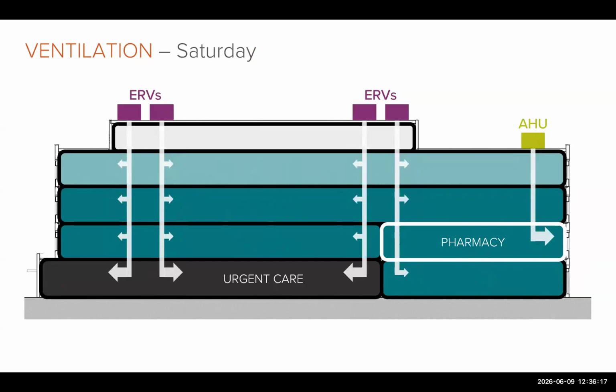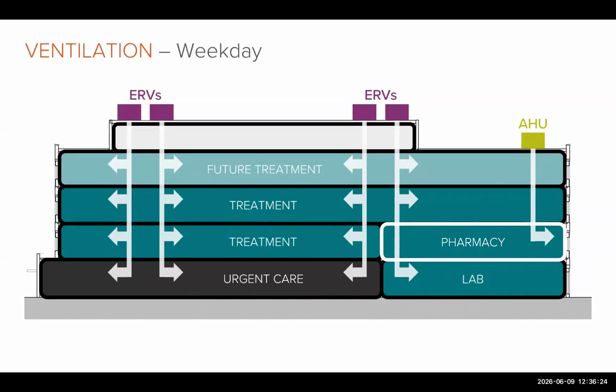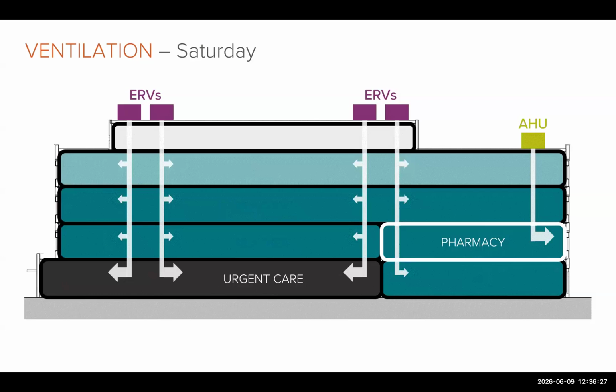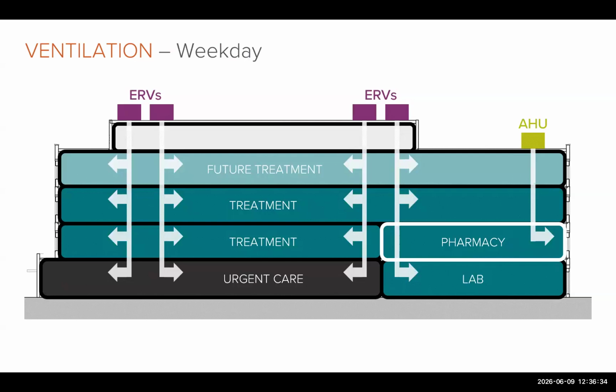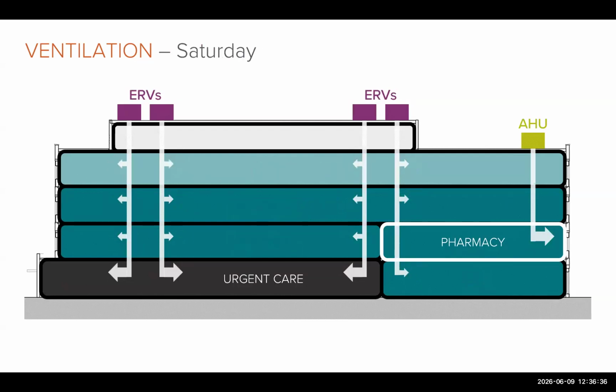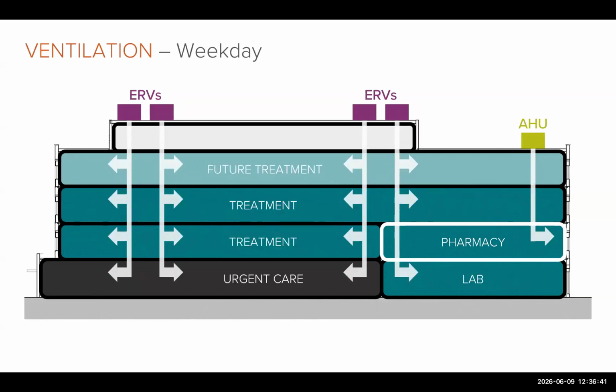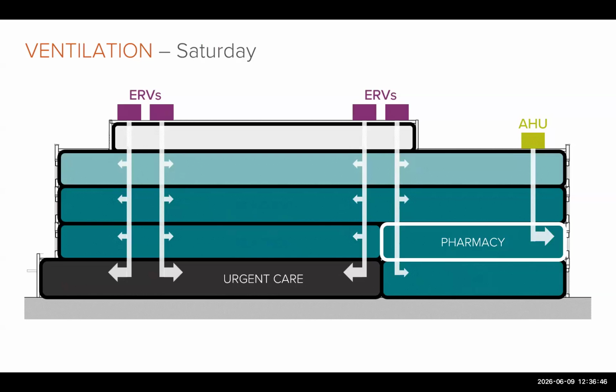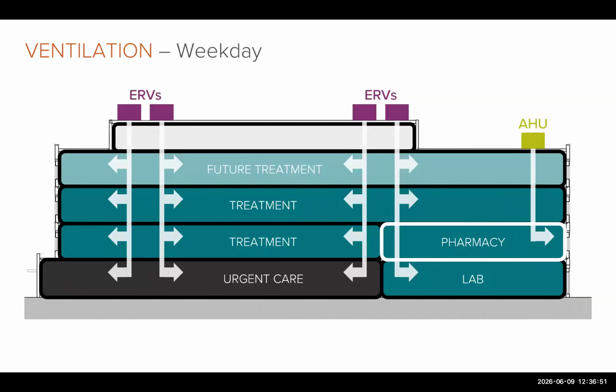Here's a ventilation diagram comparing the amount of ventilation provided by the ERVs to the amount provided by the pharmacy air handling unit. The ERVs are about 87% efficient, whereas the pharmacy AHU is only around 50% efficient. Because of the chemicals being compounded in that pharmacy, the pharmacy has to be exhausted at 3 times the code required rate of other spaces, and it has to run all the time. So from an energy perspective, this was a big hit to the project.